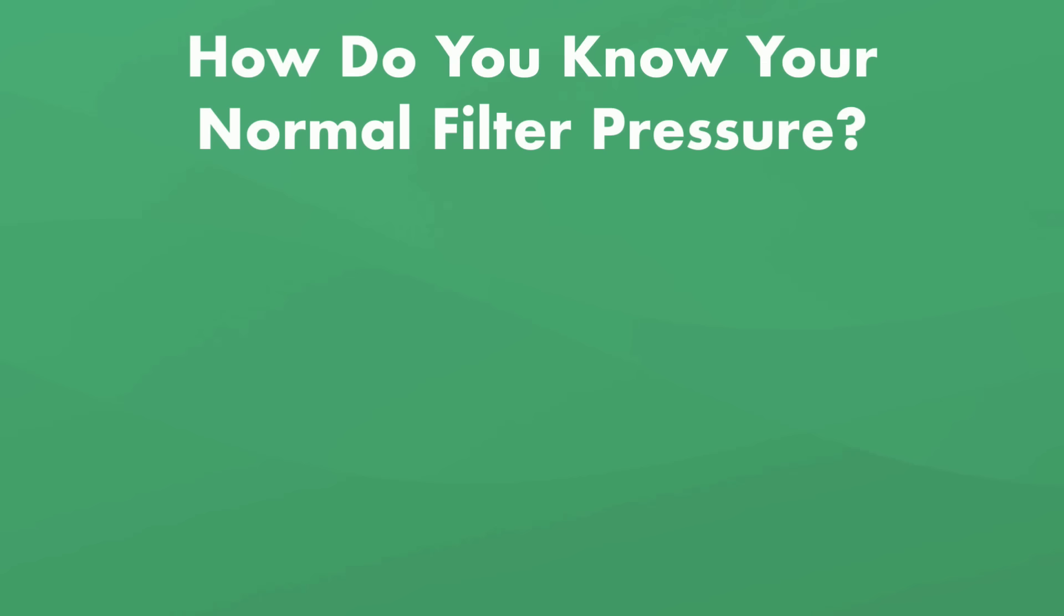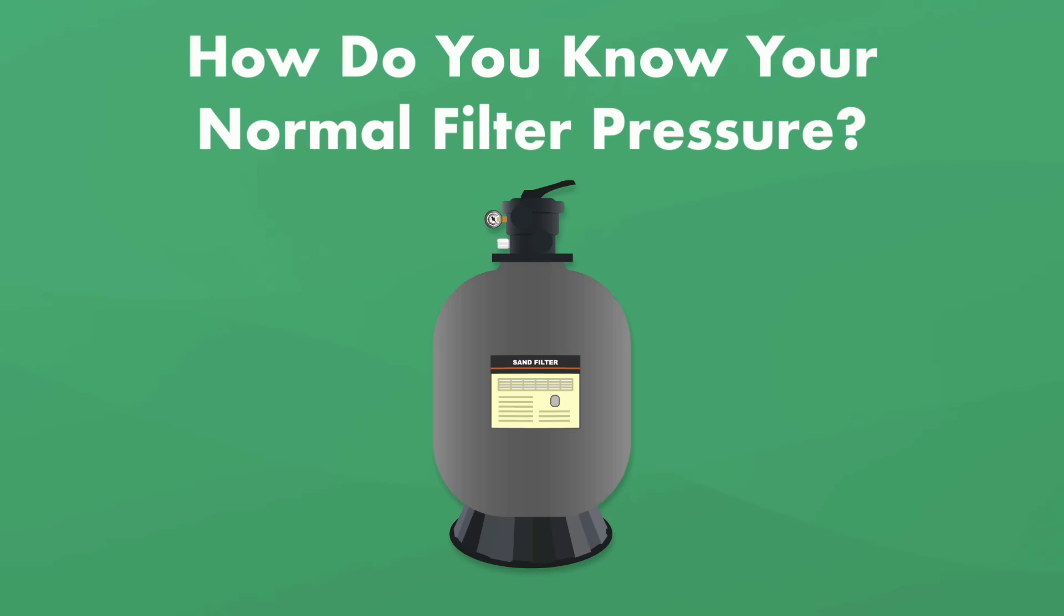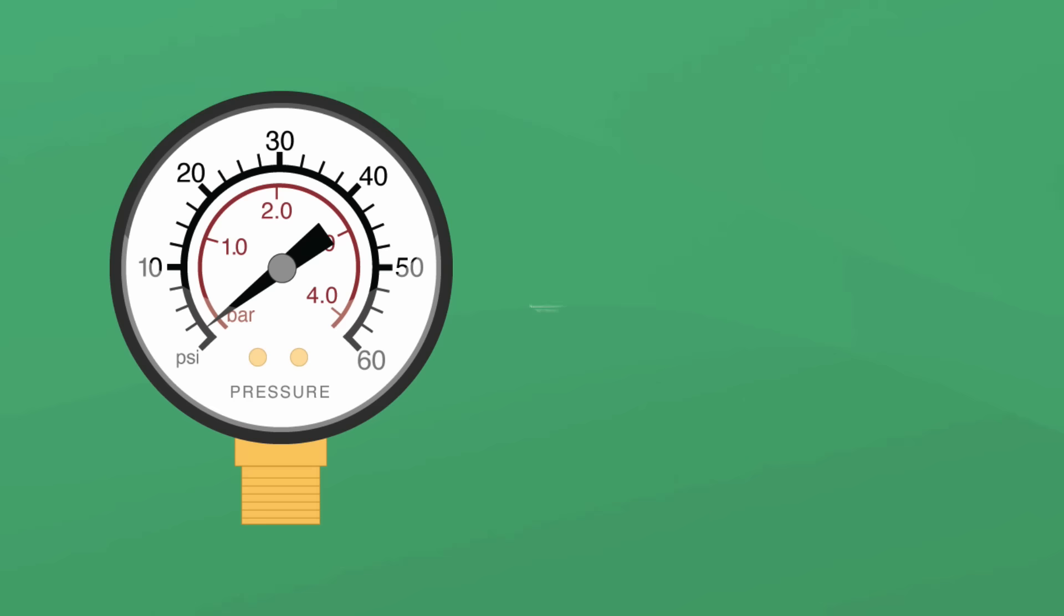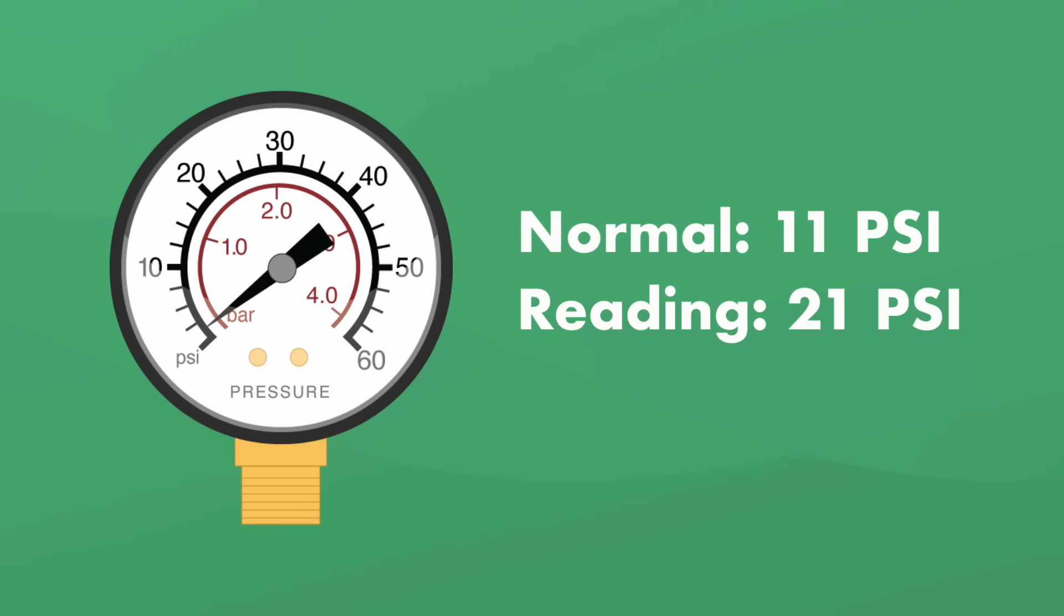How do you know what's your normal pressure? Well, right after you backwash your filter, take note of the pressure gauge. In most cases, it should read between about 10 and 15 psi. That's your baseline. If your normal filter performance is 11 psi and you notice your pressure gauge reading 21 psi, it's probably time to backwash.